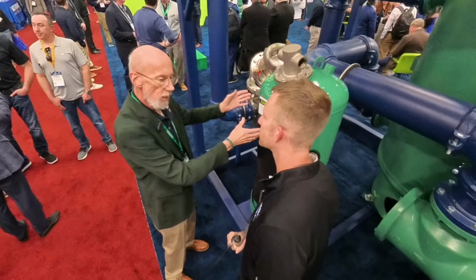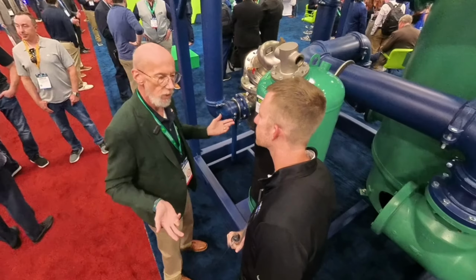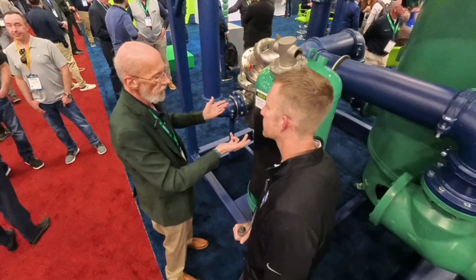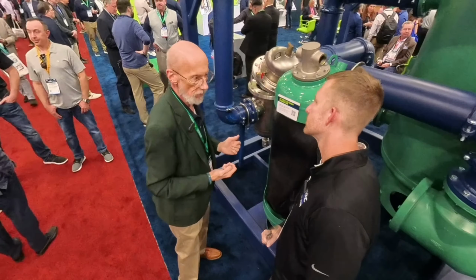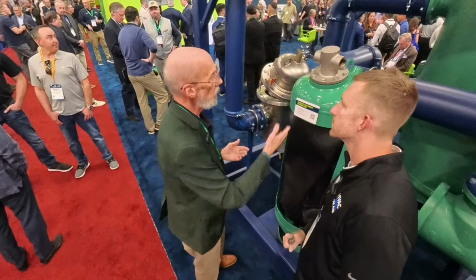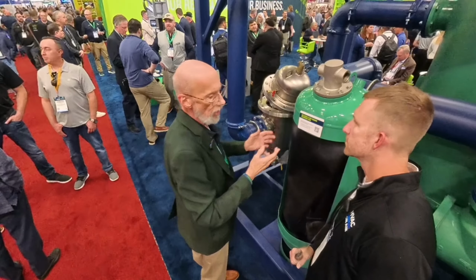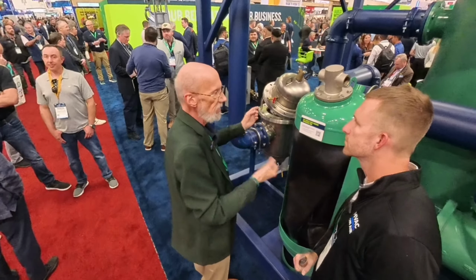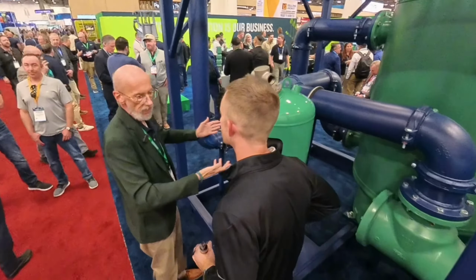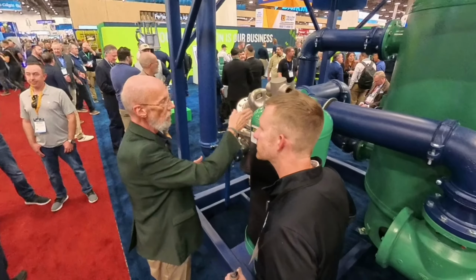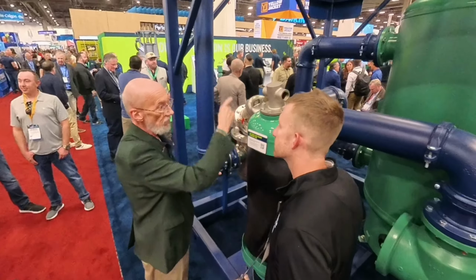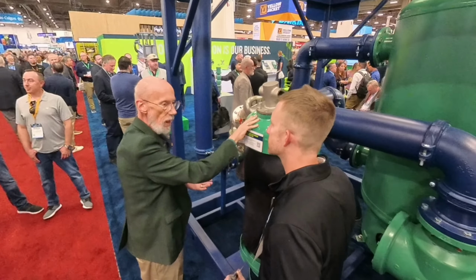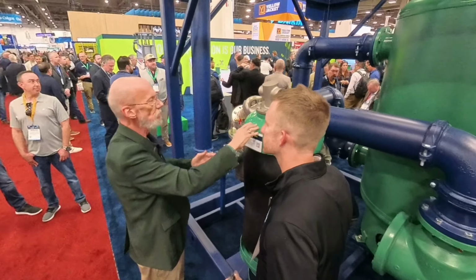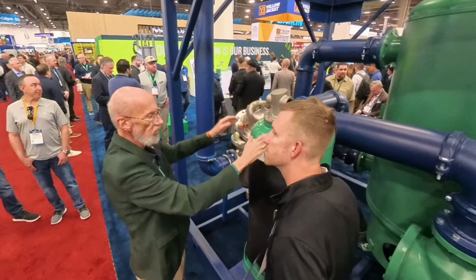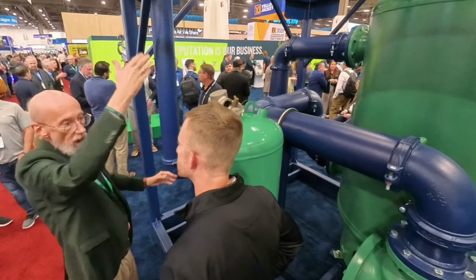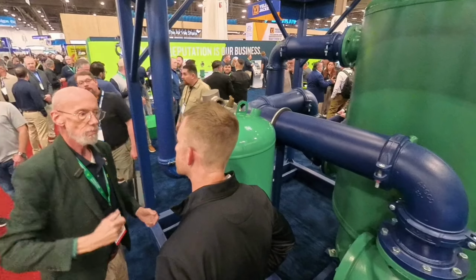From a sizing standpoint, you size this exactly like you would any other expansion tank. The only difference is it pipes in differently. The other thing that has to happen is you have to have a bypass valve around it. On a normal expansion tank, if the expansion tank goes bad, you valve it off, take it out, and do what you've got to do, put the new tank in, you're up and running. With this, because the water goes through it, I have to have the bypass. So if there's a problem with the tank or I need to check the bladder in it, I can open the bypass, close this off, do what I need to do to the tank, but I still have domestic hot water going to the building.